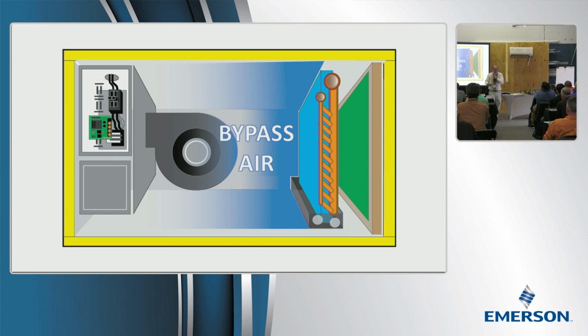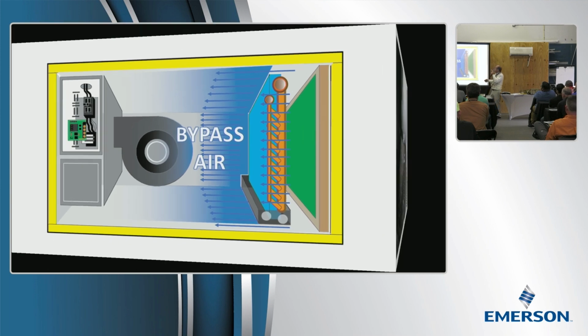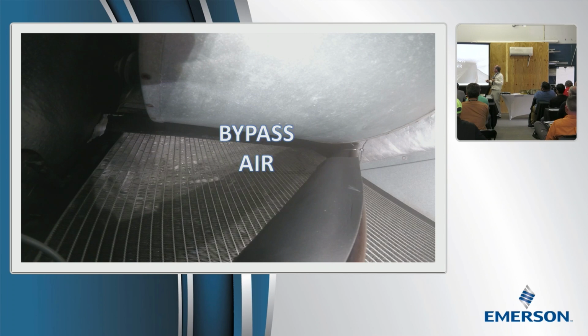Bypass air. We talked about one kind of bypass air, which is the bypass air from the cabinet leaks. But you also have bypass air around the coil, which is untreated air that will get the cabinet wet. If you've never seen it, this is a movie of it. And what's happening here, you can't see vapor, but you can see a little bit of a cloud right there. And what this is doing is it's getting this blower all wet.